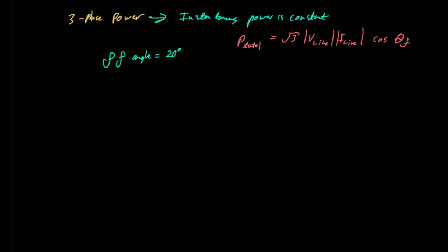If you continue to add equipment, would you have to then add more? Yes. And this is not a static thing. As you shut some equipment off, like if you run equipment only certain times of the day, you will actually change your power factor. So another thing that's often done is to try to run your heavy equipment at night when power rates are lower. This is another game that's played. And these capacitors are storing energy which can be used at other times of the day. So they're actually nice from an energy storage point of view as well. So that's another thing that most manufacturing institutions will do, is they actually look at ways to run their heavy equipment at times of the day when electricity is less expensive, like in the evening.